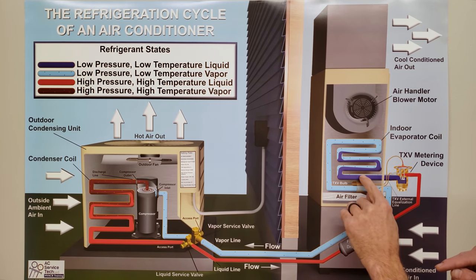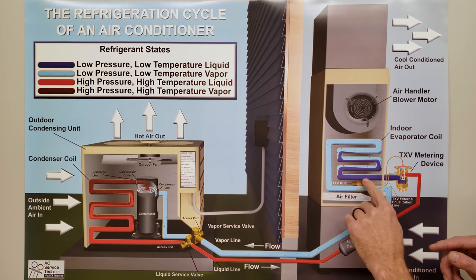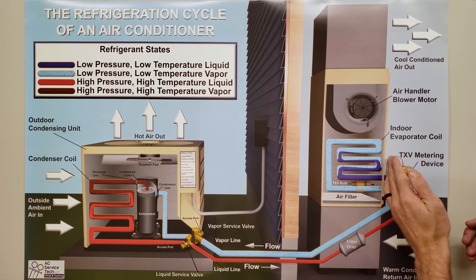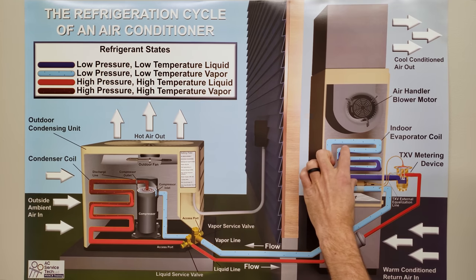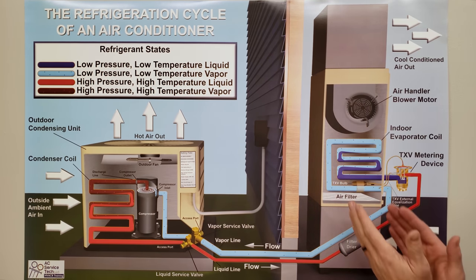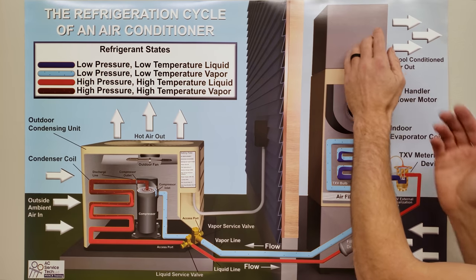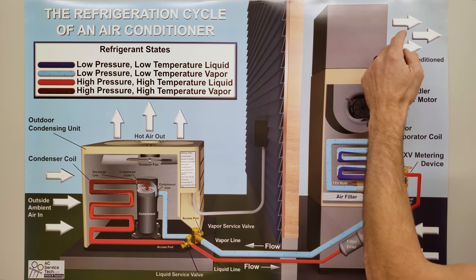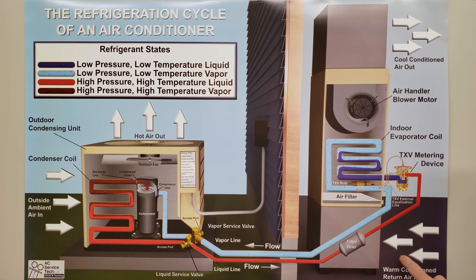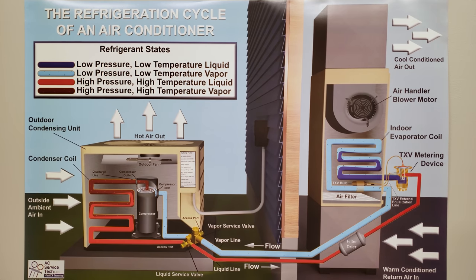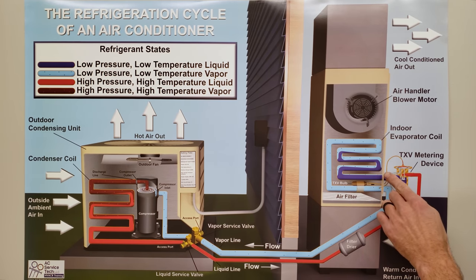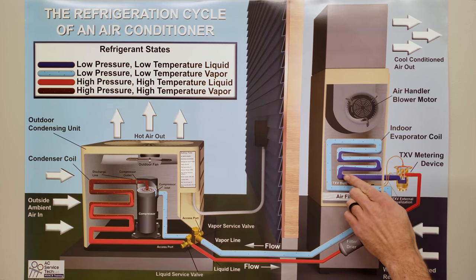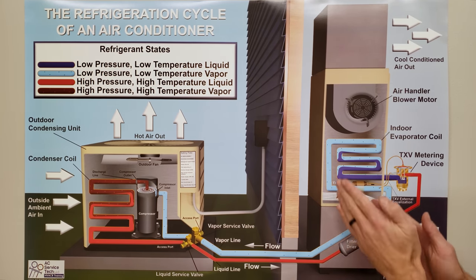Once the refrigerant is low in pressure, it expands into a liquid-and-vapor mix — about 20% vapor and 80% liquid. As it travels through the evaporator coil with air crossing the coil, the refrigerant absorbs heat from the air, lowering the air temperature. The air may enter at 70°F dry bulb and exit at around 50°F, while the refrigerant entering the evaporator coil may be around 40°F.